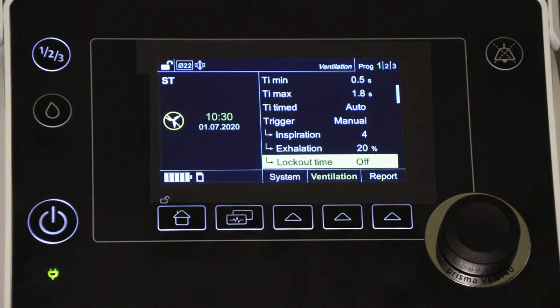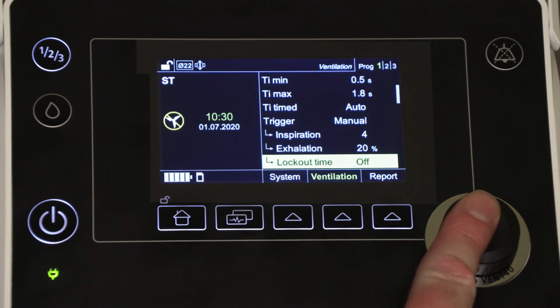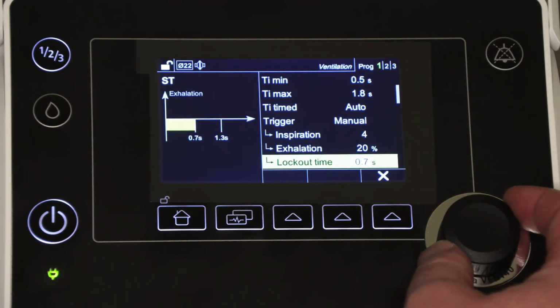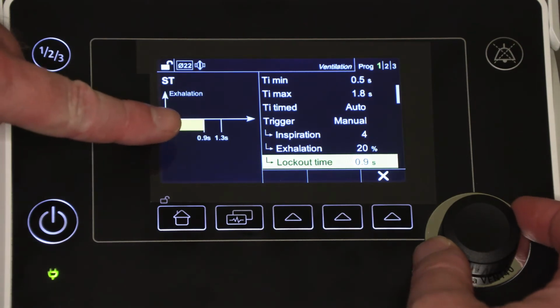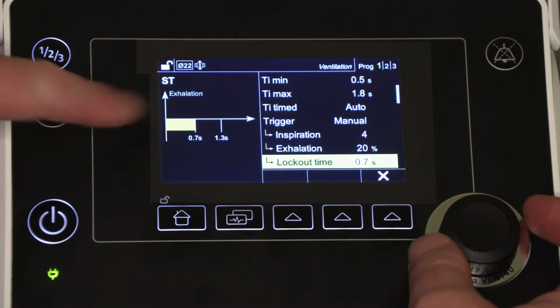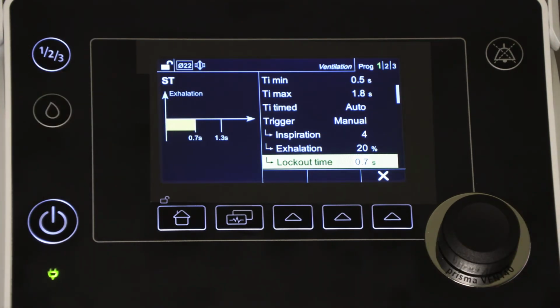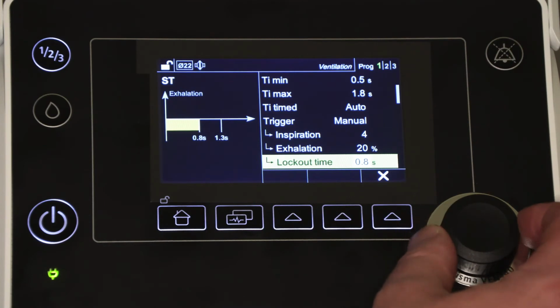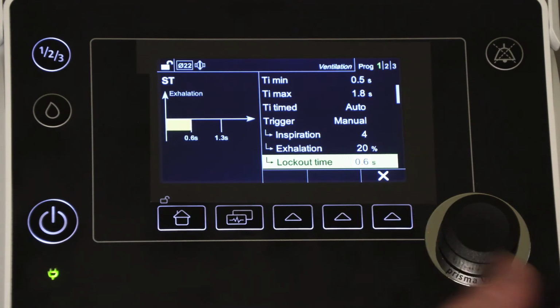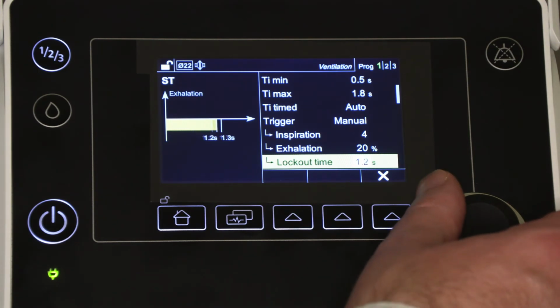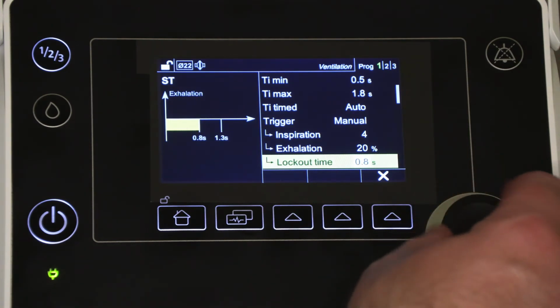The lockout time is a feature that can help prevent auto-triggering by the patient. It can be left off or it can be turned on and a lockout time can be set. The lockout time is the portion of the beginning of expiration where attempts at inspiration will be ignored and not cause prismaVENT to trigger IPAP. The device has an automatic lockout time of 0.5 seconds, but this time can be extended manually with this setting if required.